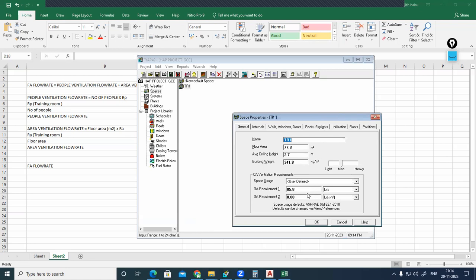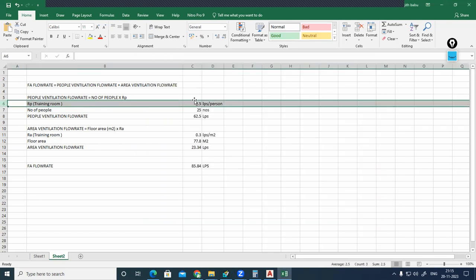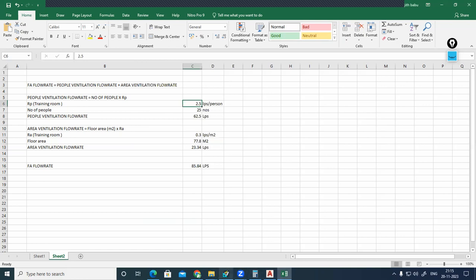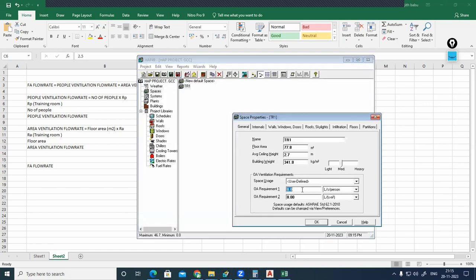Okay. The next option: you can give the liter per second per person value and the liter per second per meter square value. Liter per second per person is Rp. Liter per second per meter square is Ra. These two values we can provide here. The remaining calculation the software will do in the background. For example, for the outside air requirement, liter per second per person, how much is it? We have taken from 62.1, 2.5 liter per second. You can provide it here, this one will be 2.5.